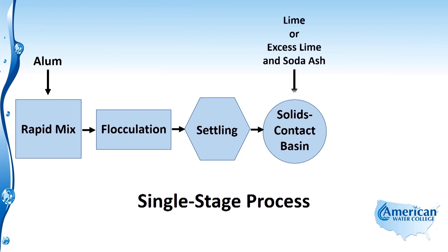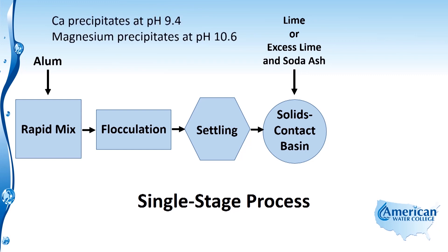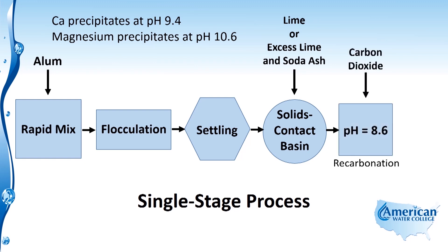From the settling basin, the water flows into a solids contact basin where we add either lime or excess lime and soda ash, depending on the makeup of the water and treatment objectives. Calcium begins to precipitate out at a pH of 9.4, so if hardness is primarily due to calcium, we add lime and raise the pH to 9.4. If magnesium is greater than 40 mg/L, we use excess lime and soda ash to raise the pH to 10.6.